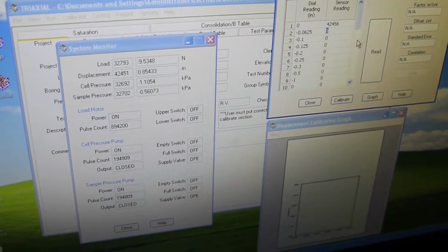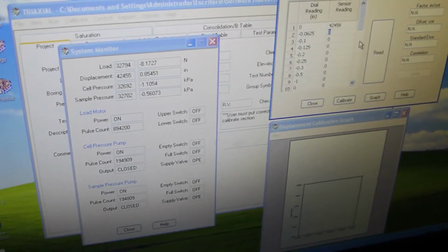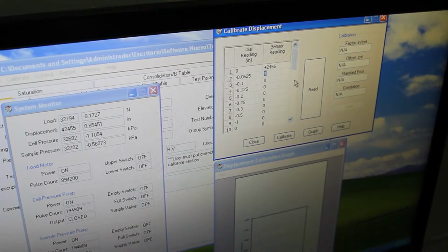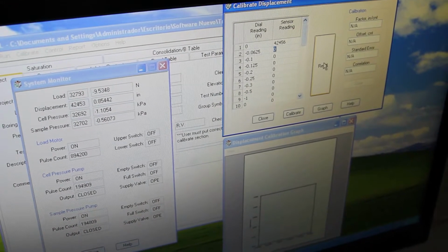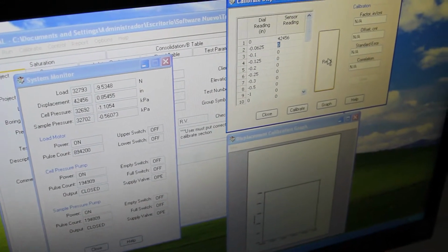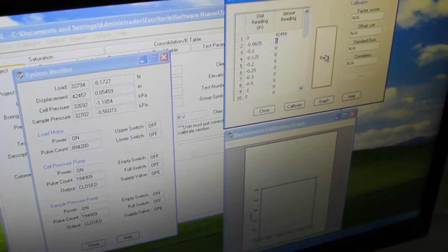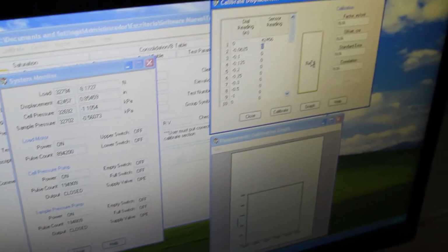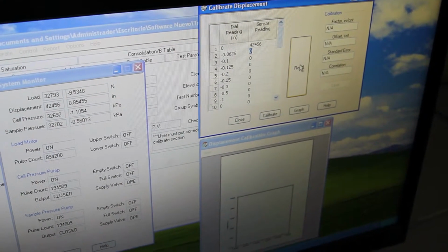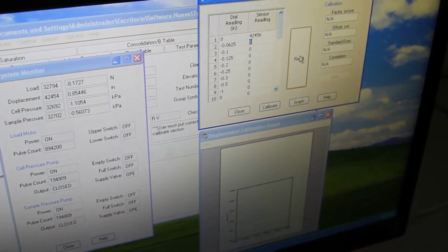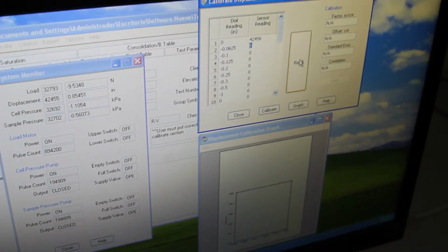So next what I'm going to do is insert the blocks, and that corresponds to each one of these readings, and do read, and I go to the process. I'm going to have 9 points in here all the way. The readings are in inches just because the gauge blocks are in inches, but they could be in any set of units that you are comfortable with.